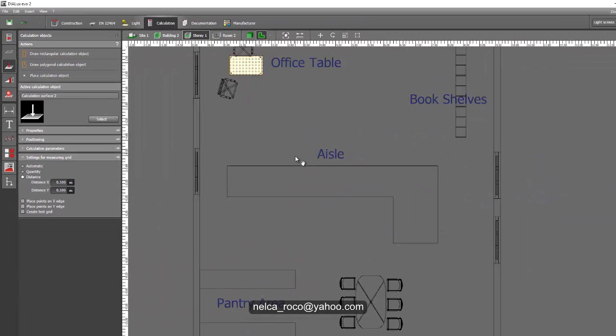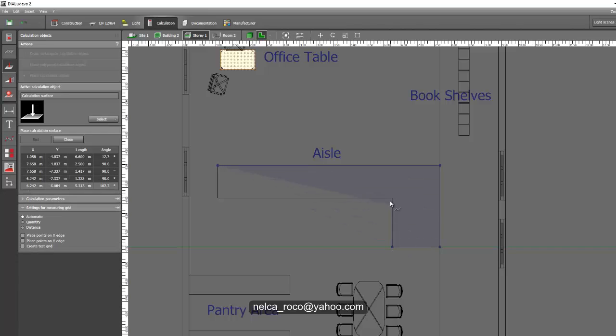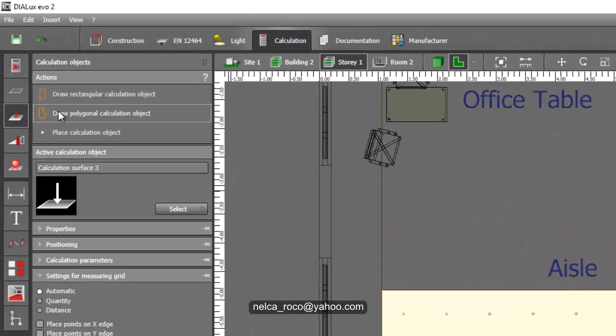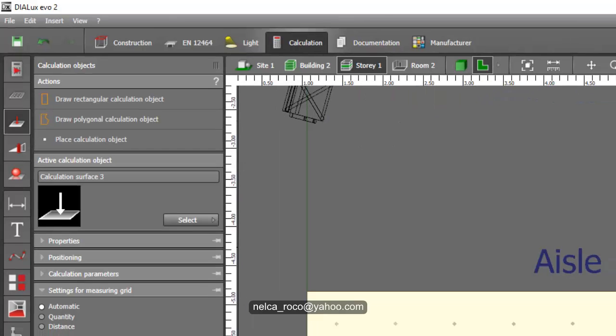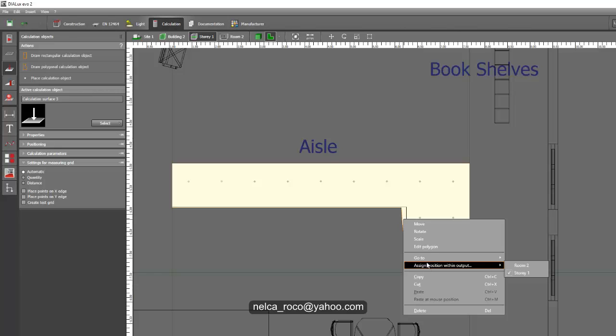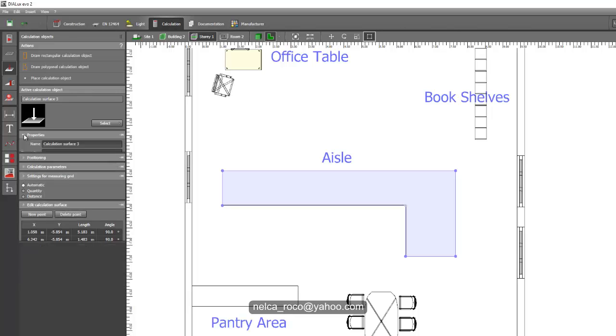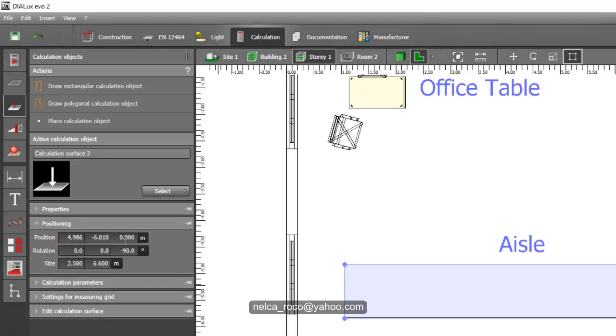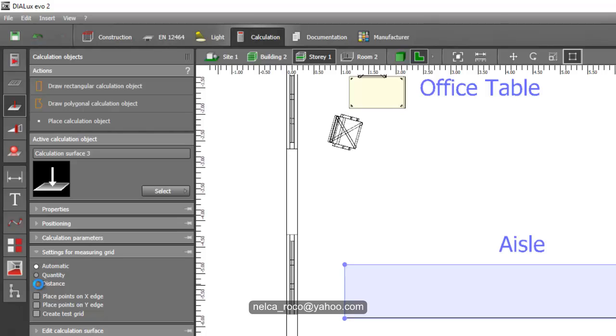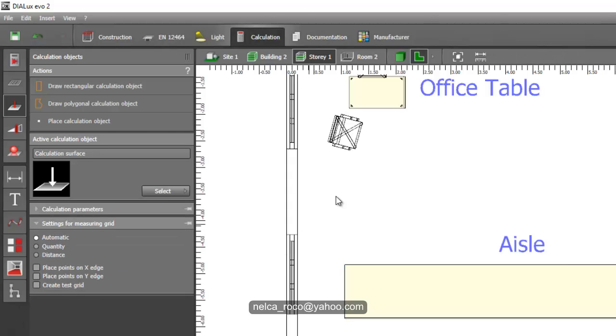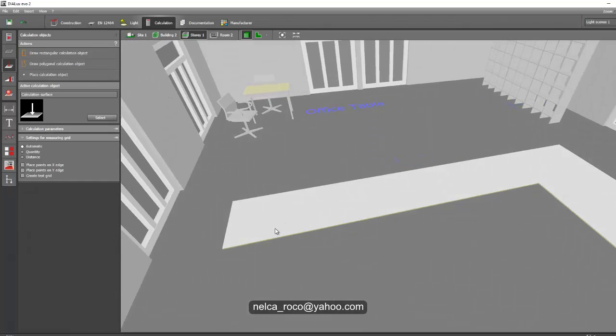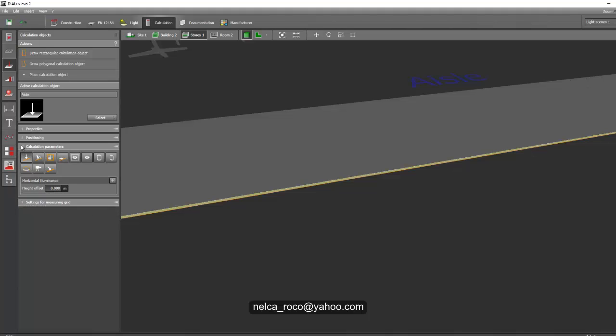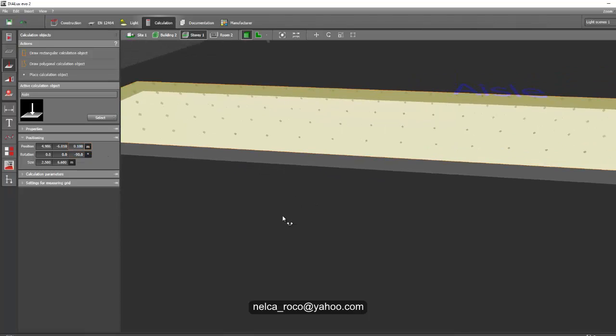For example, in the aisle, if you want to add another calculation surface on the aisle, a separate one, then just create a calculation surface like this. Make sure you select polygon side instead of rectangular. If you made a mistake, just right-click and edit polygon. The positioning, you can say this is aisle or corridor, and the positioning would be zero. The calculation parameters, yes horizontal. If you want to edit the spacing of the points, you can make it 0.2 by 0.2.